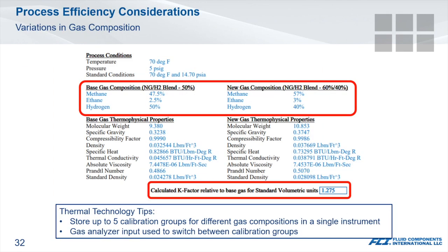Variations in gas composition will impact the gross calorific value of any fuel being burned. The gas density, which is one of the variables in the simplified mass flow equation, will also change. By properly addressing these variances, we can ensure that our flow measurement is optimized to maintain the appropriate ratio between air and varying blends of natural gas and hydrogen.